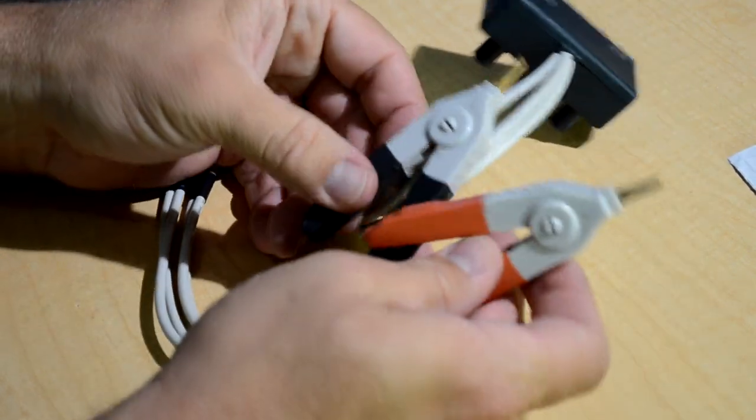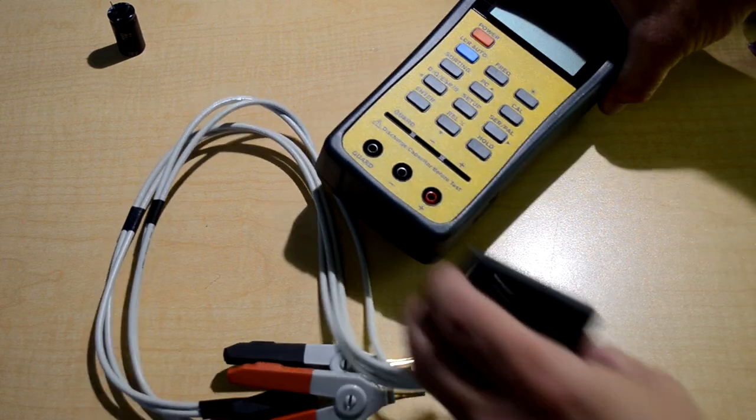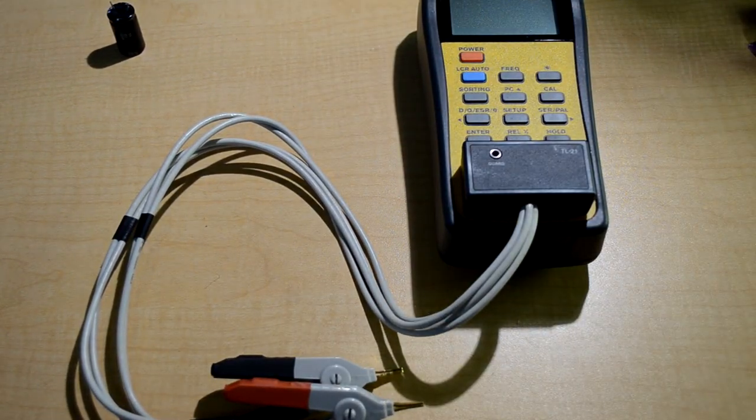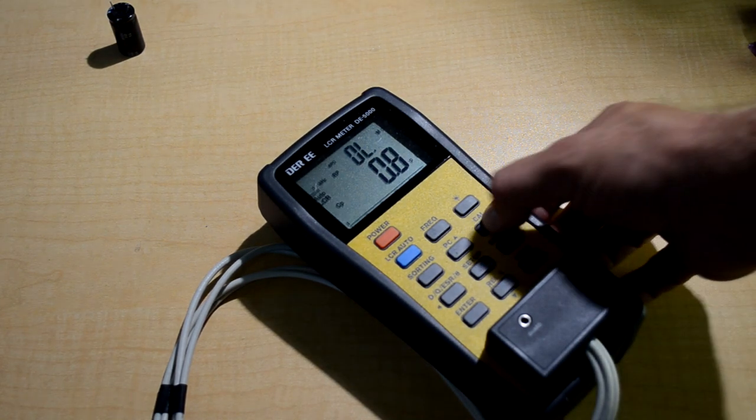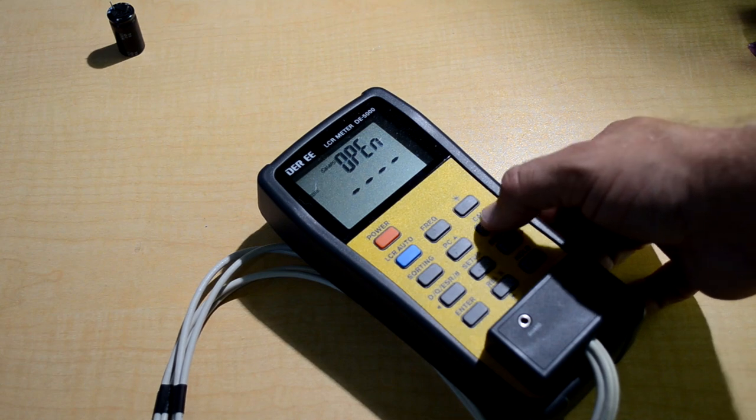So now we've got everything tested or put back together and we really just need to run a test and make sure that our new cables are checking out and will work for what we want to do. So I've got the same capacitor as before and we'll run a check on that capacitor. First, I need to show you how to calibrate your meter because we definitely need to do that now that we've changed the cables.